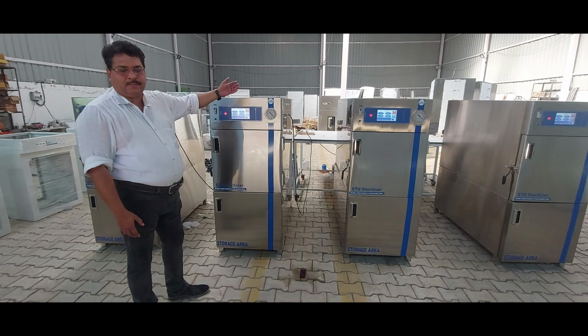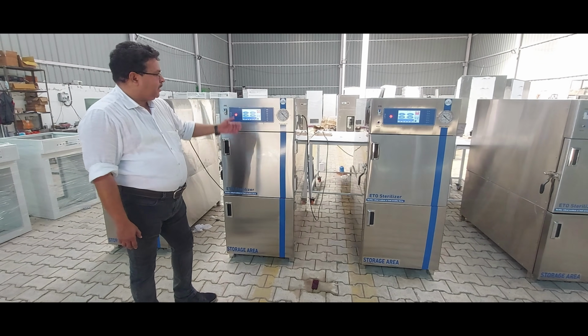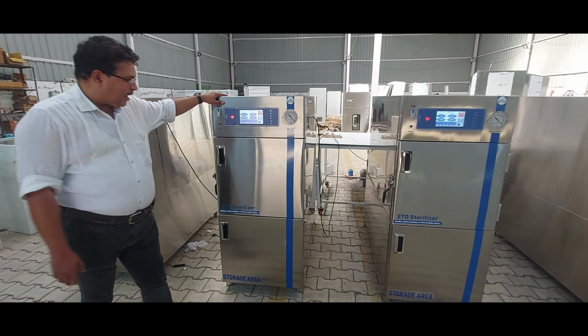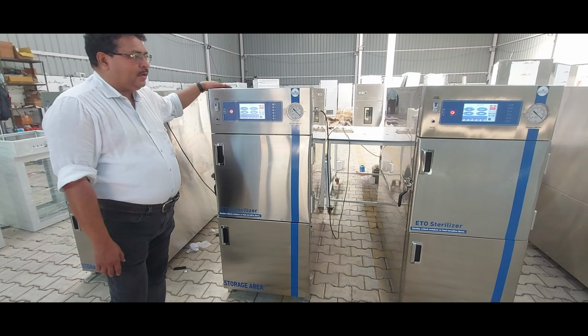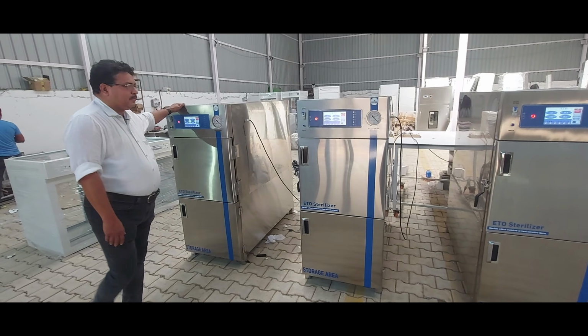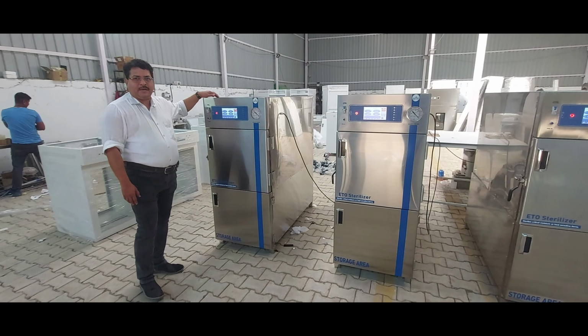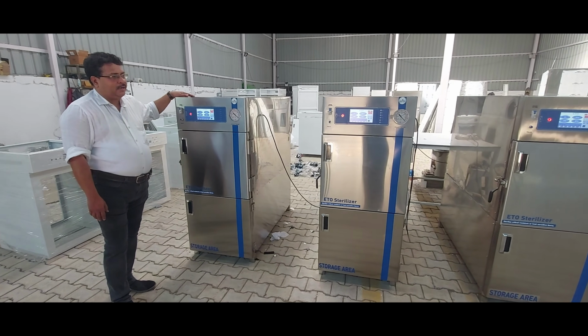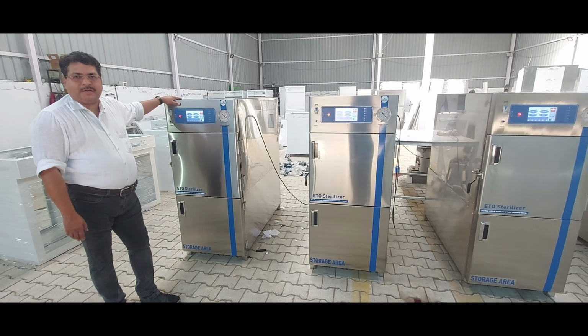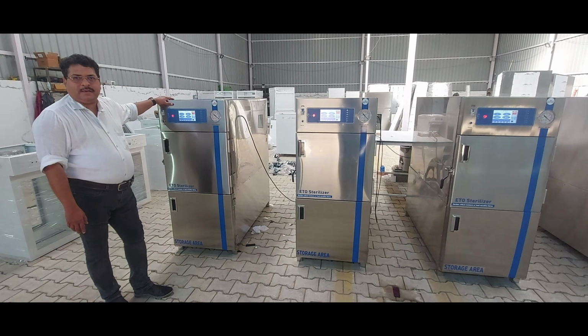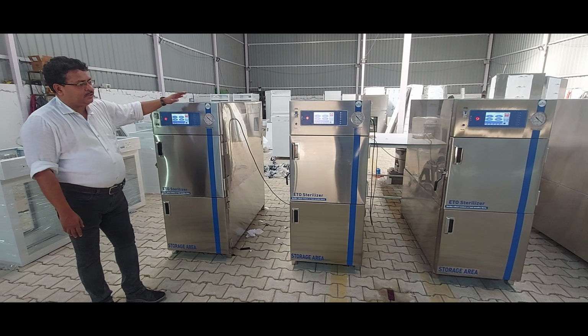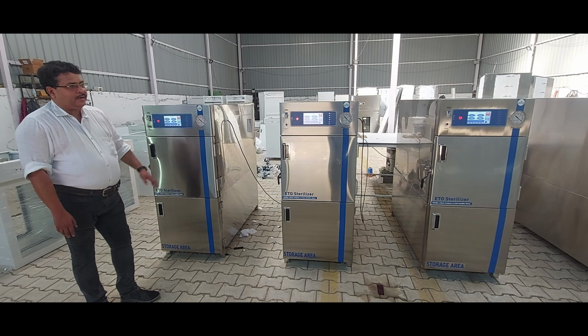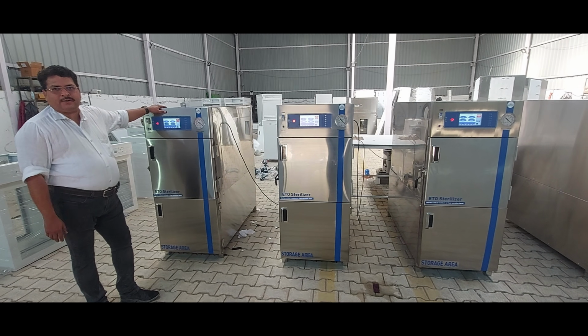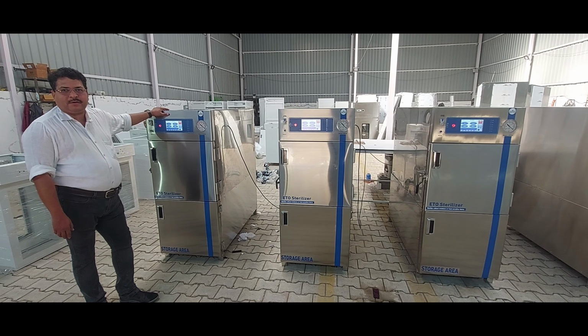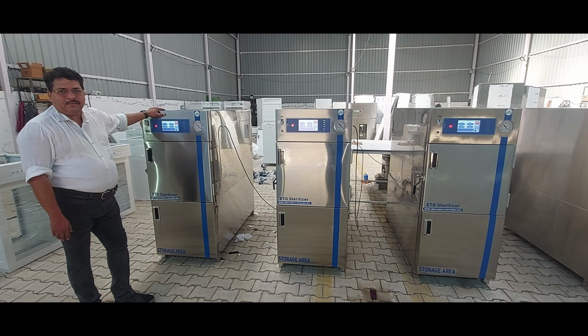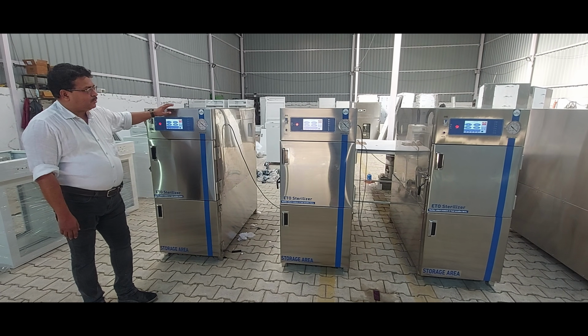How ETO sterilization works. Low-temperature process. ETO sterilization operates at relatively low temperatures, 37 to 63 degrees Celsius, making it suitable for materials that could be damaged by heat. Gas penetration. The gas can penetrate through various materials and packaging, ensuring thorough sterilization. Controlled parameters. The process involves carefully controlling gas concentration, temperature, relative humidity, and exposure time.